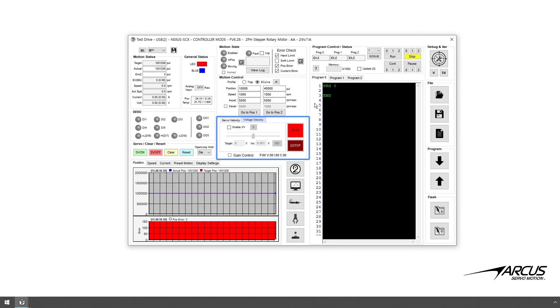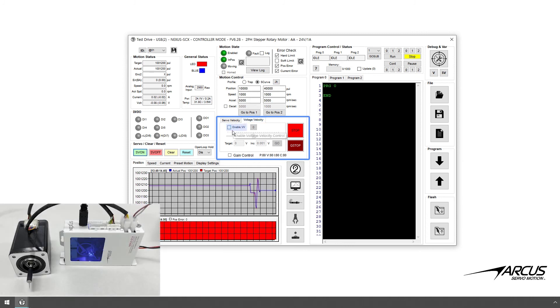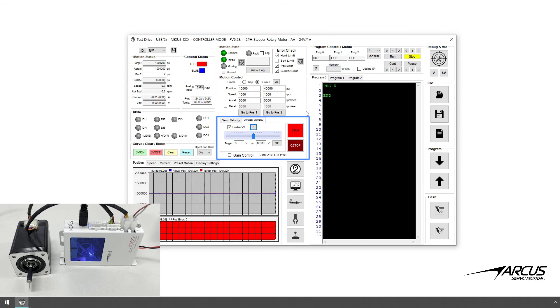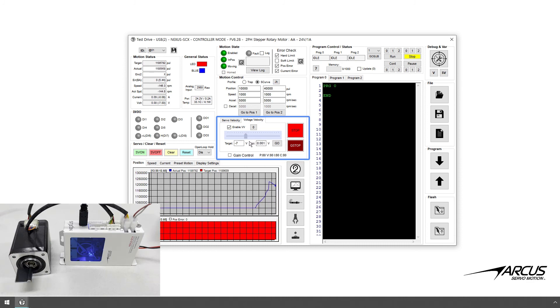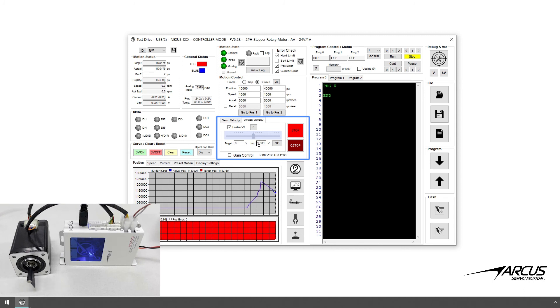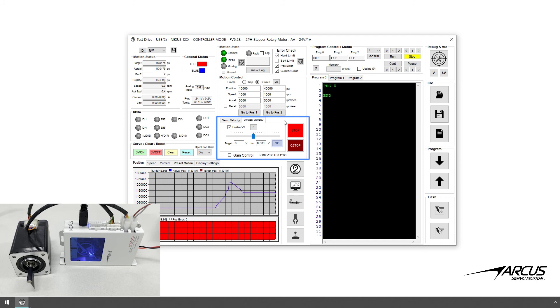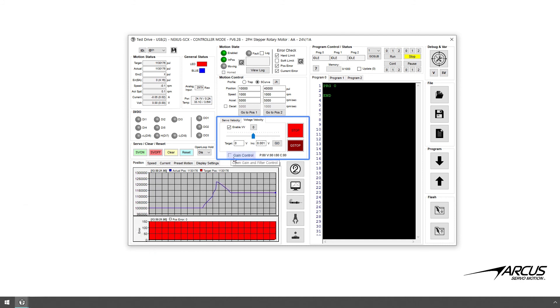Select the voltage velocity tab. On the voltage velocity control, the velocity is controlled with voltage control. Click the enable voltage velocity checkbox. The zero button is to set the voltage value to zero. You can use the slider or the actual target velocity to set the voltage value. The increase increment value sets how fast the velocity is changed — the smaller the value, the slower the voltage change and the quicker the response. The go button is used to go to the manually entered value.